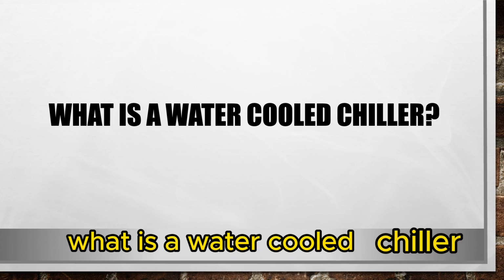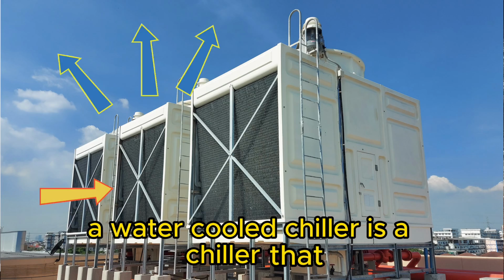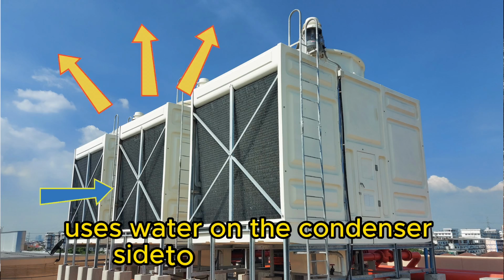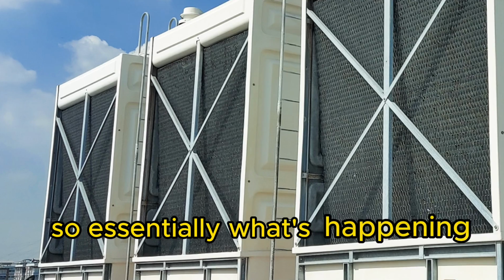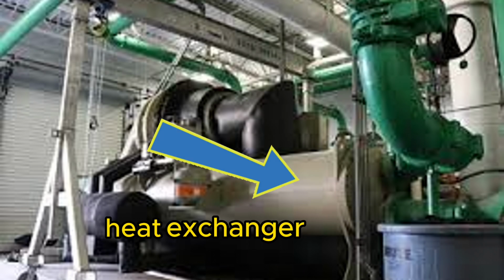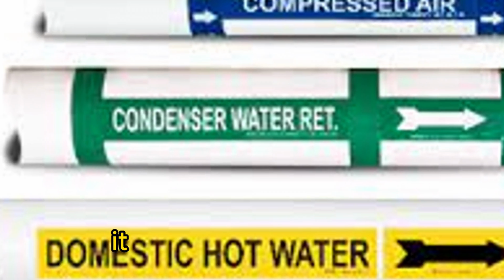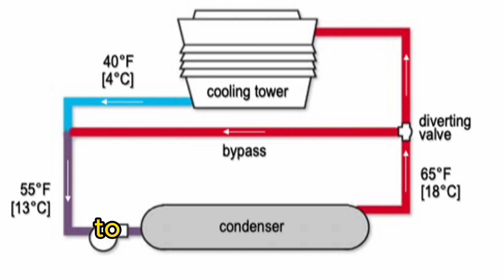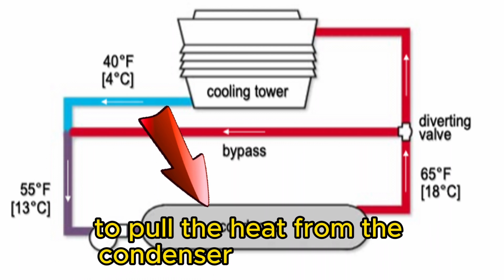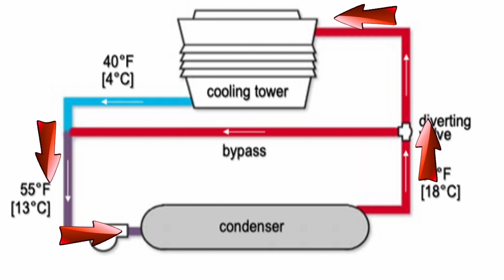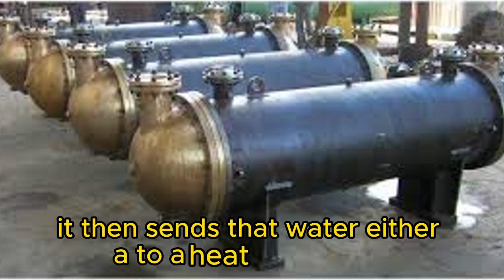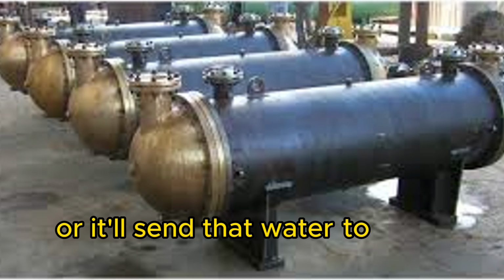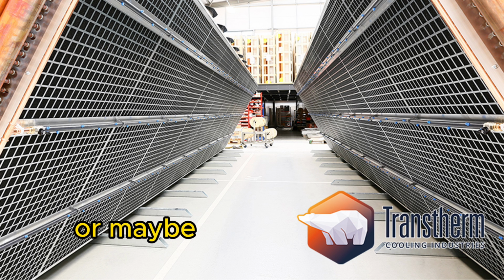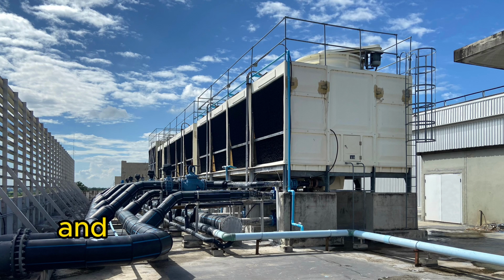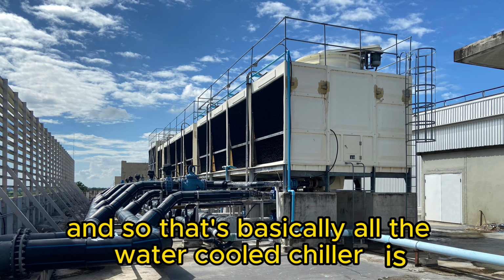What is a water-cooled chiller? A water-cooled chiller is a chiller that uses water on the condenser side to reject the heat. So essentially, you have a heat exchanger on the condenser side. It uses water or glycol, depending on what kind of system you have, to pull the heat from the condenser circuit on the refrigeration system. It then sends that water either to a heat exchanger, or to a dry cooler, or maybe even to a cooling tower. And that's basically all a water-cooled chiller is.